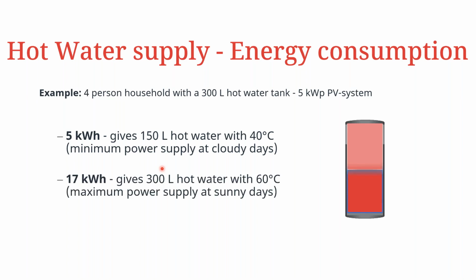But for the entire 300 liters of storage to be heated up to 60 degrees, it would require about 17 kilowatt hours for this particular function. And therefore, this is the maximum supply that would be required on sunny days. So as far as the day curve with load management plus the Ohmpilot, it would look like this.